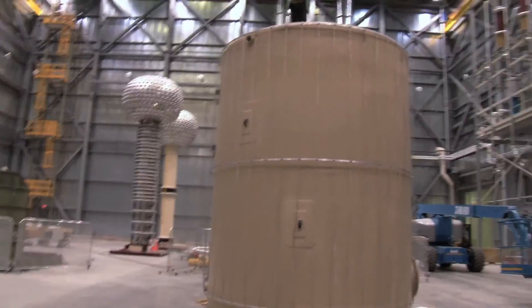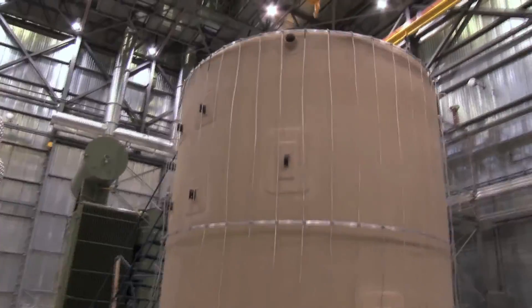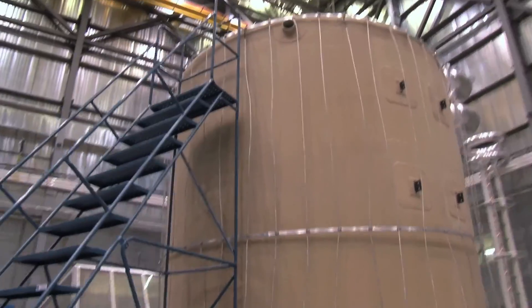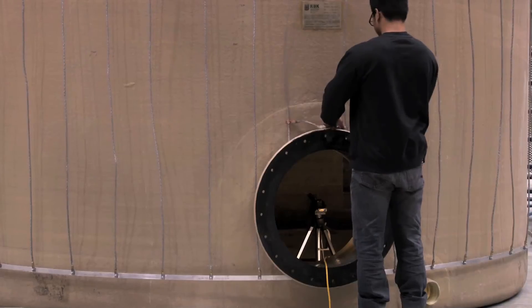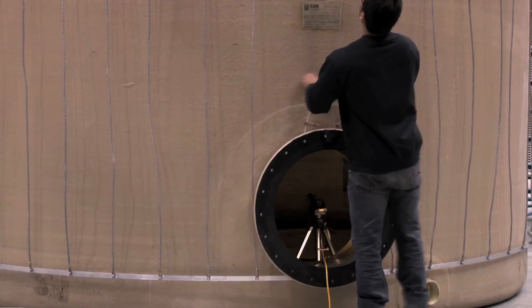Tuned for lightning frequencies, the patent-pending design is made to resist induced potentials beyond the capabilities of this laboratory and can suppress sparking on the inside of the tank due to all indirect lightning strikes with return stroke current up to 250 kA. The shield additionally employs the patented streamer-inhibiting technology which further limits the tank's exposure to direct lightning strikes without increasing the height of the tank.